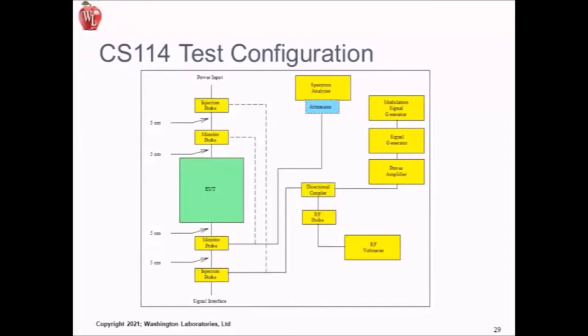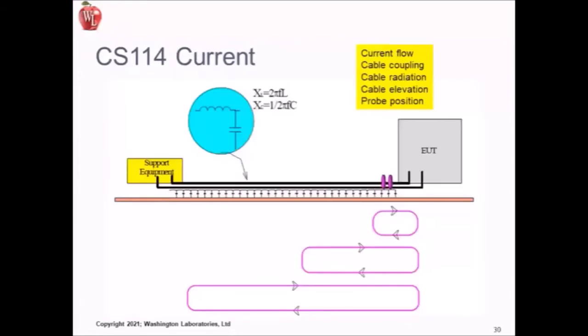And here we have a modulation signal generator and a power amplifier. And in this case, we've got a directional coupler, so we can monitor the RF output or the amount of drive level that we're going in. And simultaneously, we have a spectrum analyzer measurement receiver, so we're detecting the amount of drive current going into the equipment under test. And again, you don't want to overtest, so you're always monitoring the amount of current that's going in there so you hit the target level. This is sort of the way the current couples into the equipment under test.